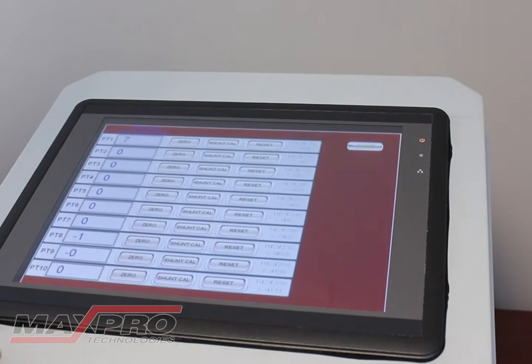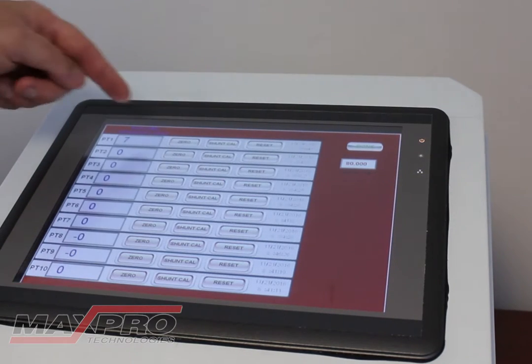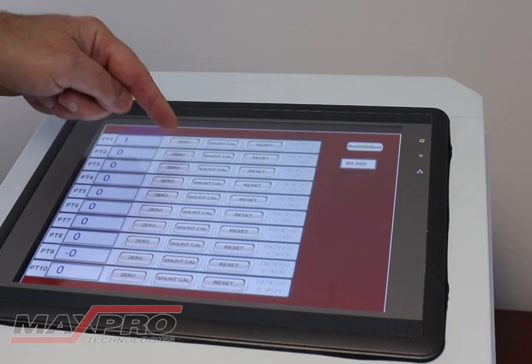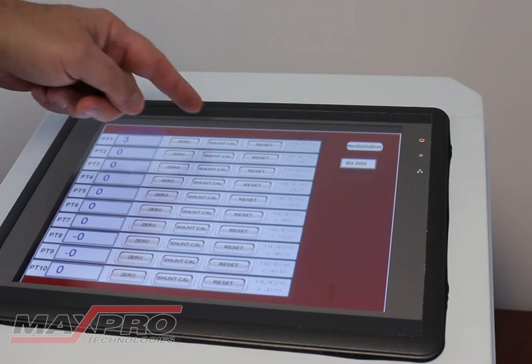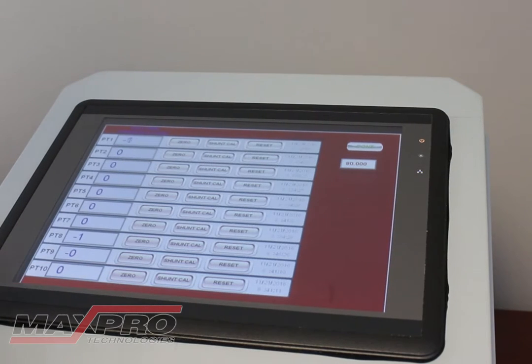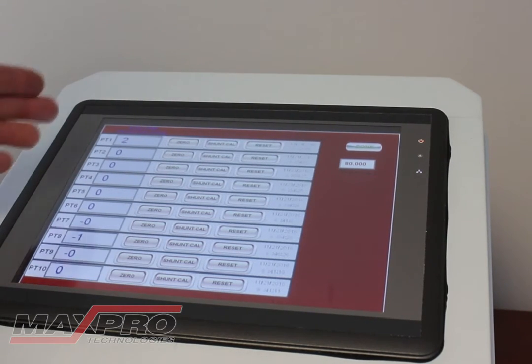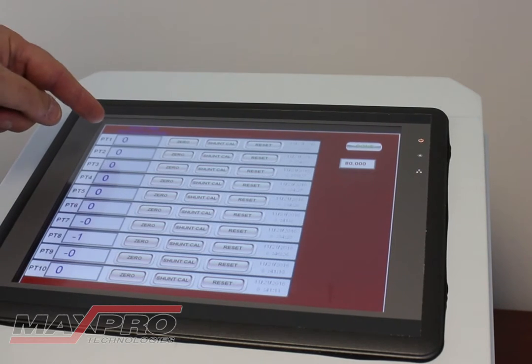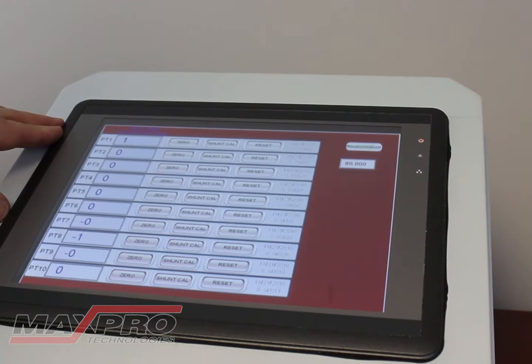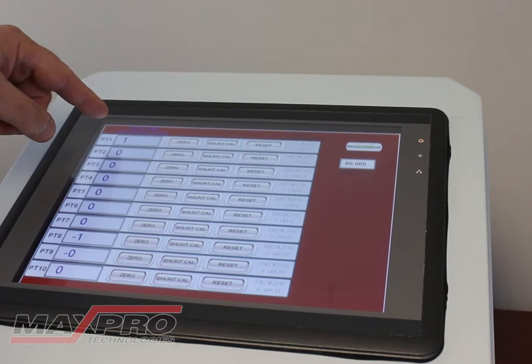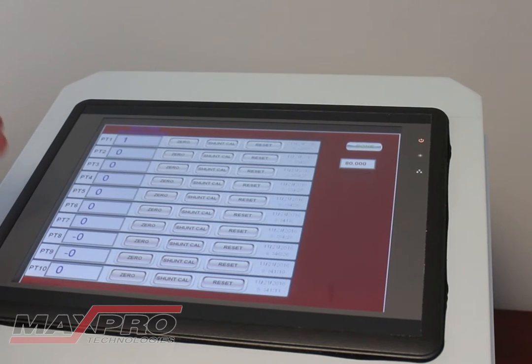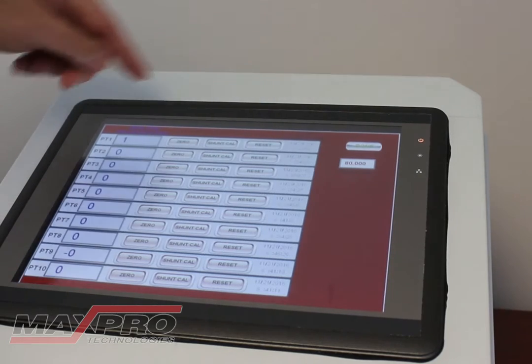Then there's a calibration button, so you can go in and zero all the transducers out. There's also a shunt cal, which calibrates the pressure transducer to the box. When you press that, it simulates 80% of the range — this is a 30,000 psi box, so it would take it up to 24,000 psi, calibrating the two together. That's what you do on the calibration screen.